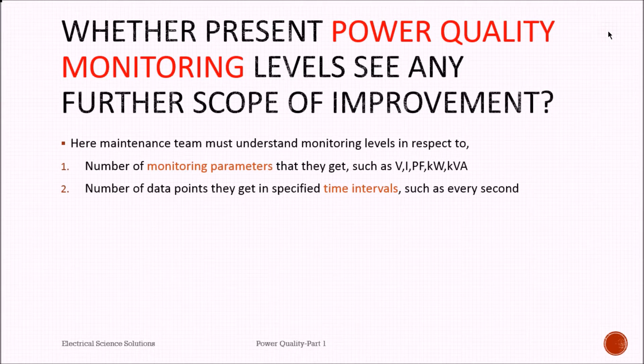Third one is the type of information about V and I, voltage and current, such as what is the harmonic content, whether we are getting a true RMS value or it is just an average value or a RMS value. What are the values that we are able to obtain, that is maximum, minimum values. Then voltage regulation, whether we can arrive on a calculation of voltage regulation. Can we get the crest factor, can we get the K factor, can we capture the sags and swells, because the time that sag and swell occurs is a very small short time, that is in milliseconds, whether we are able to capture the interruptions as well. So after this, a team must arrive to a conclusion whether any further improved monitoring is required, specifically with respect to time and accuracy, because this will only help us in finding out any root cause analysis for any failure of equipment, or any other things that equipment manufacturer tells us and we can give them.